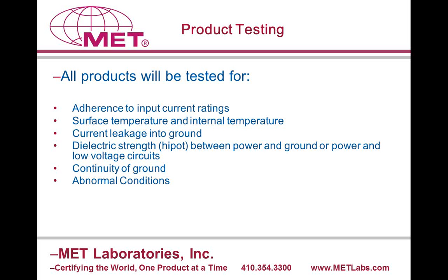In addition to looking over your product, which we call our construction review, we're also going to put your product through a rigorous battery of tests. The tests that I've listed here are done on any water-based electrical product. We're going to make sure that the current rating is accurate since it determines the size of the wiring and the electrical breakers. We're going to check the surface and the water temperatures. We're going to check for excess current. We will check the electrical separation between live circuits and ground. We'll check bonding continuity to ground, and we will do fault testing or abnormals. Every aspect of the system should have redundant fault protection so that if one thing fails, there is something else to back it up.